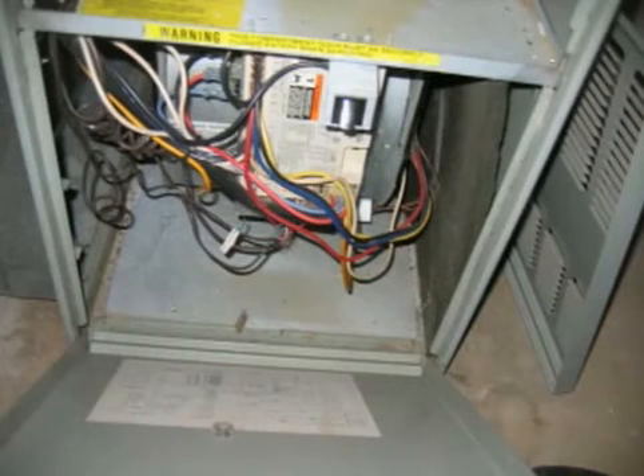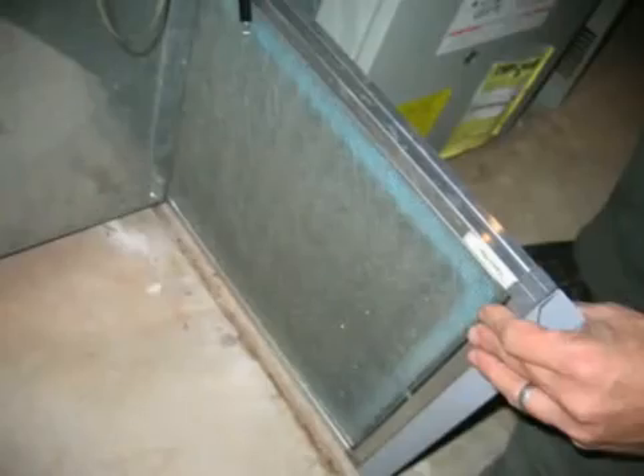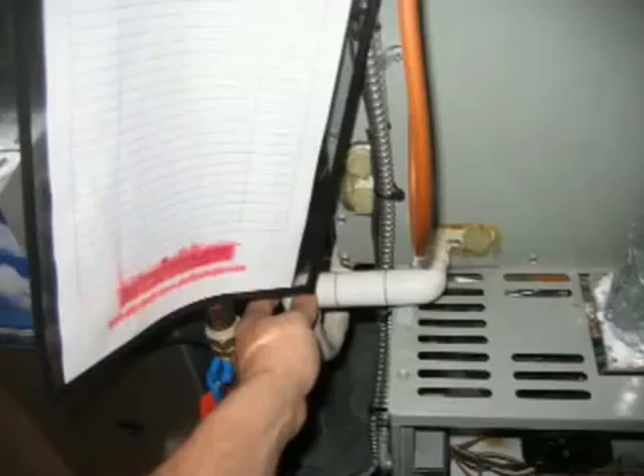Open up the blower door compartment area. Take a look, looking for signs of areas of concern. There's a UV light inside the air filter, which is great. However, it's just dirty, so there's delayed maintenance. Hasn't been serviced in a long time. That's a condition that's conducive to mold growth.